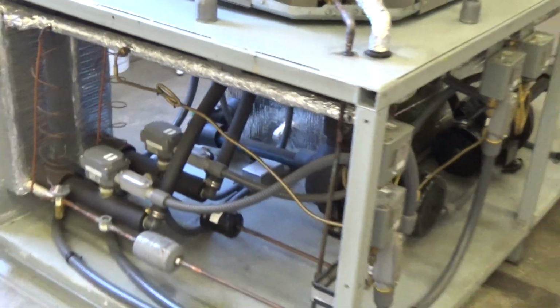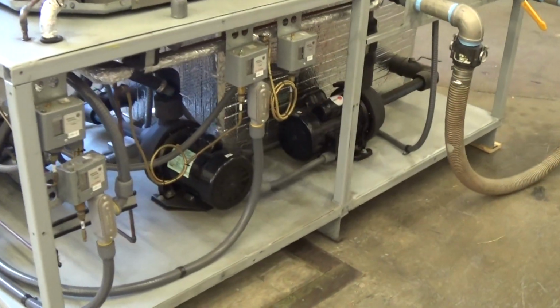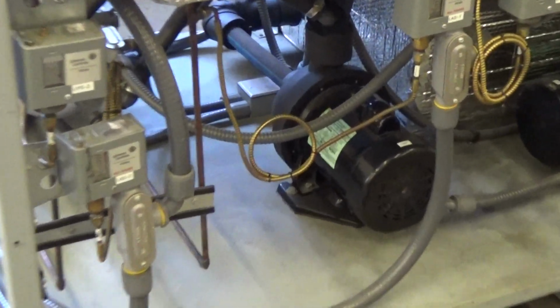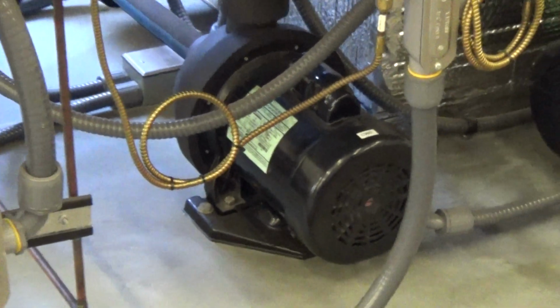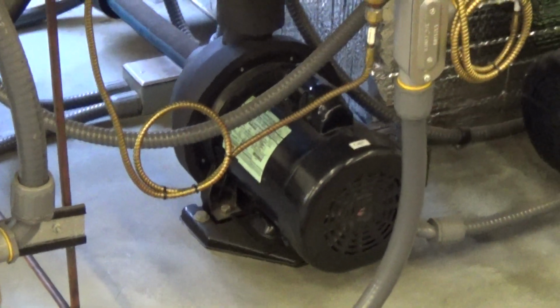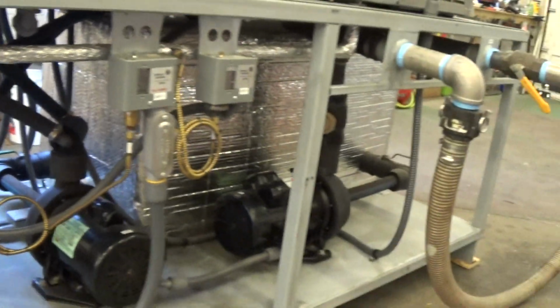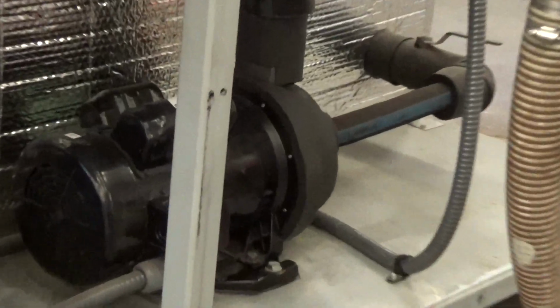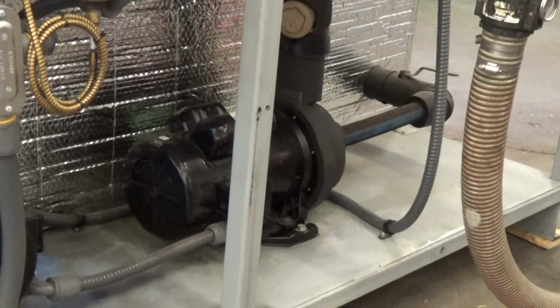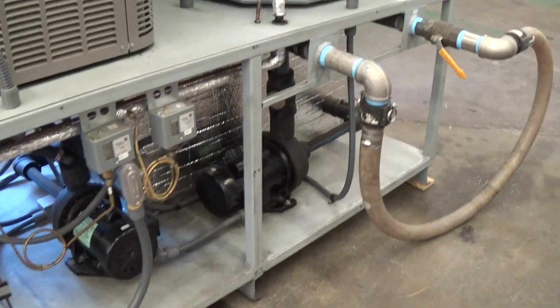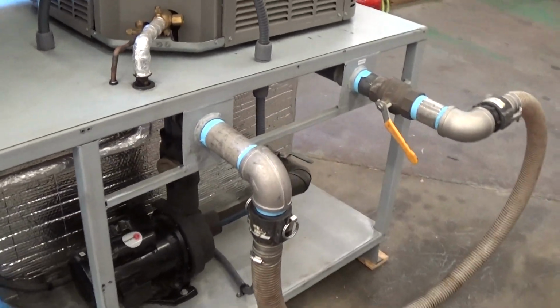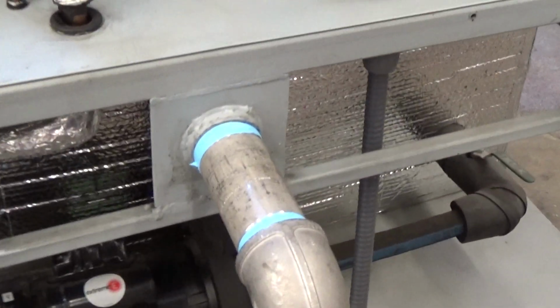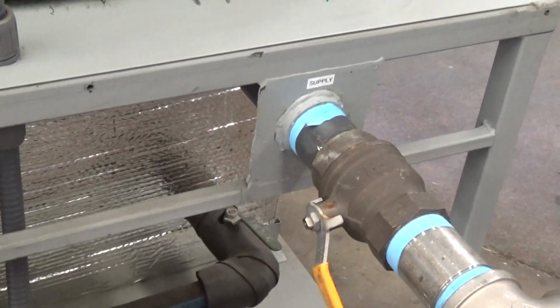One of the nice things about this is it's also a two-pump system. We have a 1/2 horsepower chiller circulation pump, which draws from the tank and then splits off and goes to both the circuit 1 and circuit 2 evaporators. Then completely separate, we have the 2 horsepower process pump here that draws from the chilled water tank and goes out to the process. Now on the back here we have 2-inch NPT connections.